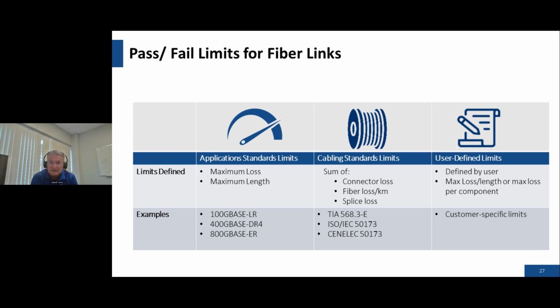So the cabling standards most commonly seen are the TIA 568. There's a typo here - it should be ISO IEC 11801, and then Cenelec 50173. These are standards that really define what the maximum loss of different events are. So they set a maximum loss for a particular connector, a maximum loss for the fiber involved in the link, and then, not commonly seen in most data centers, a maximum splice loss. So those are two standards-based limits that can be set.